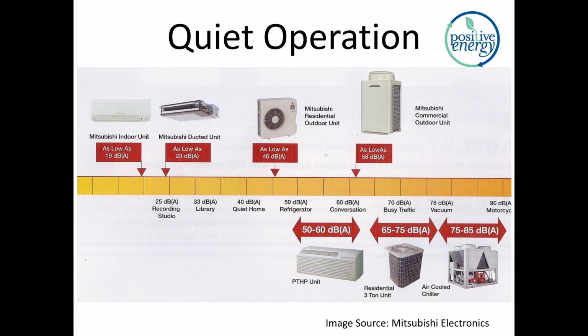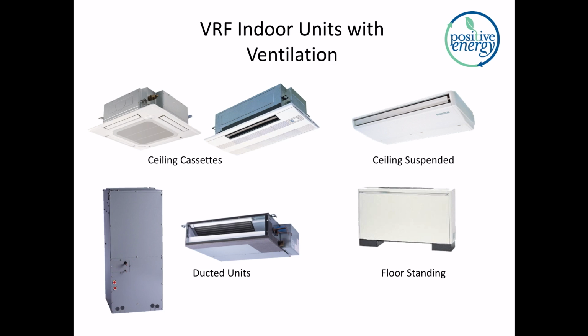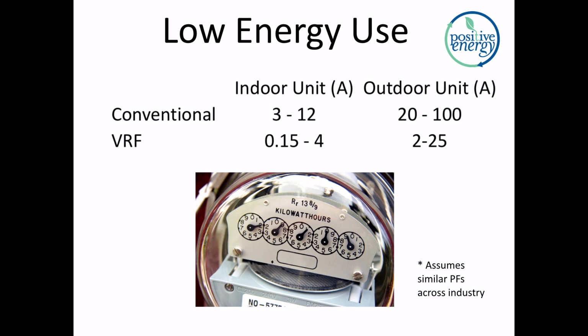Again, very quiet operation on these indoor units. Here are the ones that are compatible with ventilation air, right? So pretty much all of them, though not in all sizes of all of them. All of this equipment generally, indoor units and outdoor units, is associated with low energy use. Here's one quick way to quantify this. Looking at the indoor units for conventional, typical units are 6 to 12 amps. Some of the smaller units are only using 3 amps. Compare that to VRF. Look at that. It's like a light bulb on an indoor unit, and it goes up to about 400 watts.